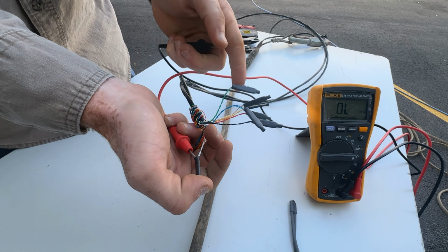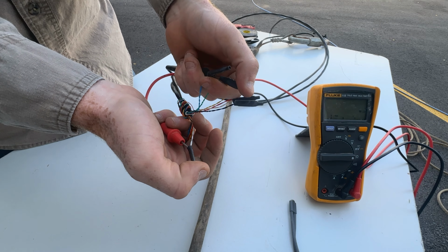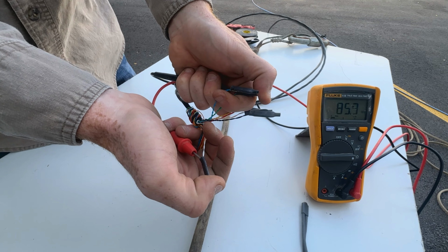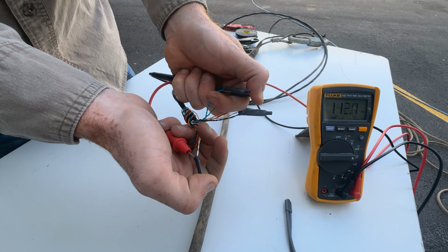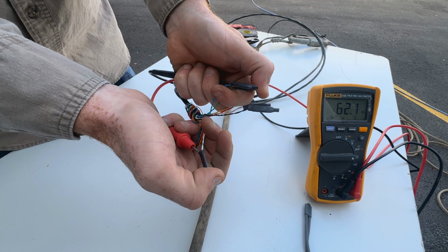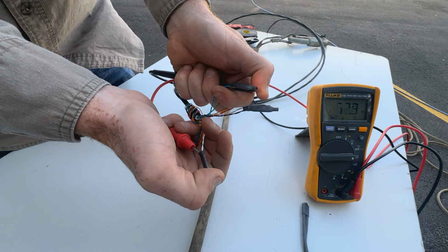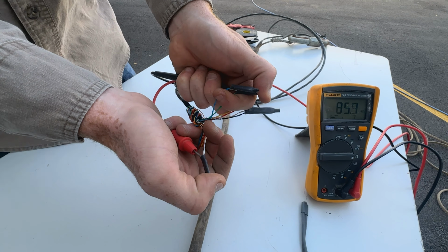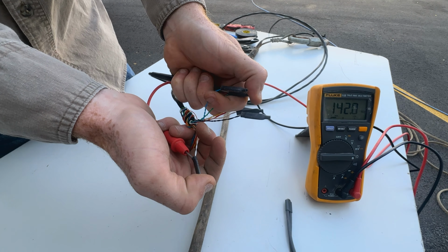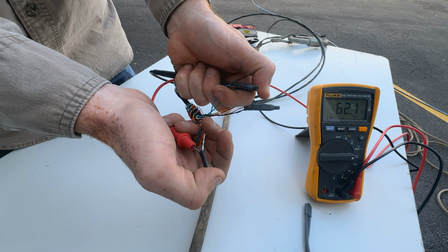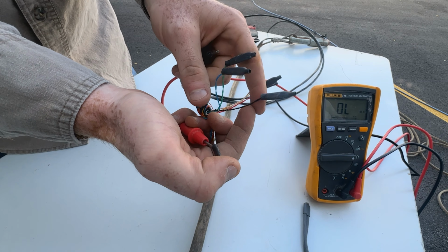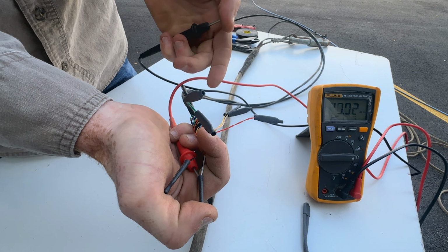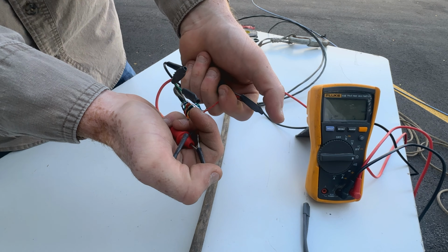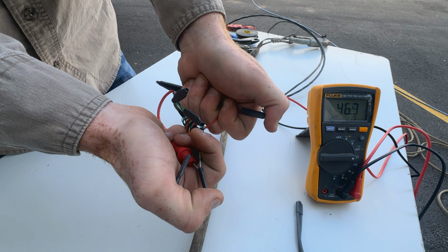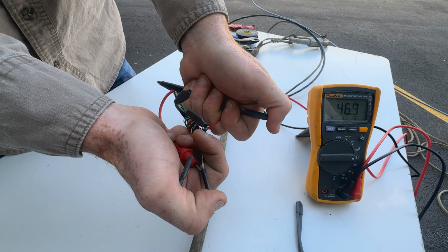Now let's check the green wire. Here is yet another example of a bad thermocouple. The number continues to decrease. If you see this, or the opposite, where a number increases, then the thermocouple is no good. Now let's check the red wire. The steady number 46.9 indicates a good thermocouple.